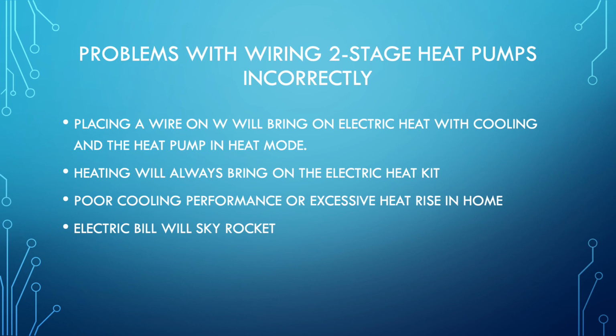So for service techs who are going out on a diagnostic, that's a clue that the wiring is going to be wrong, and the first thing you want to take a look at is to find out if there's a wire on W. Especially if it's a homeowner who decided to put in their own thermostat. They always get that wrong. So check your wiring, operationally check each mode after an installation.